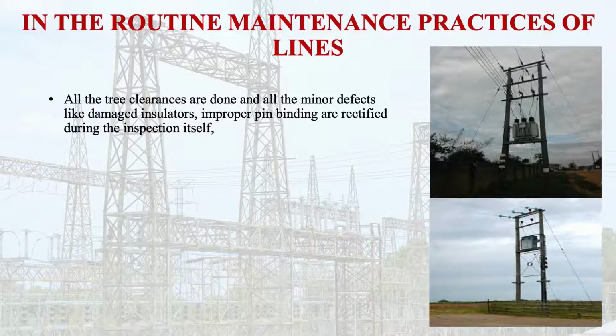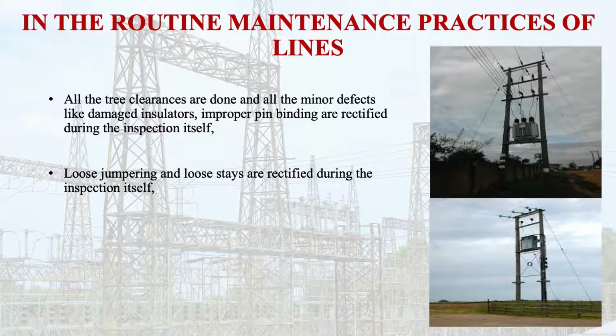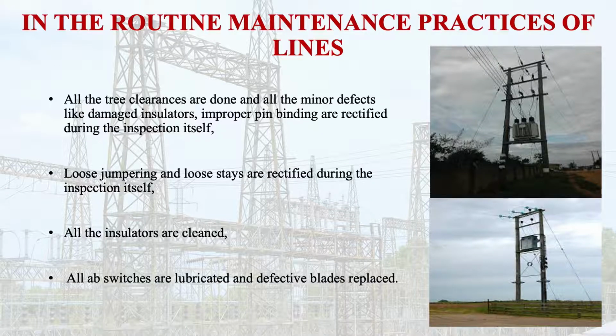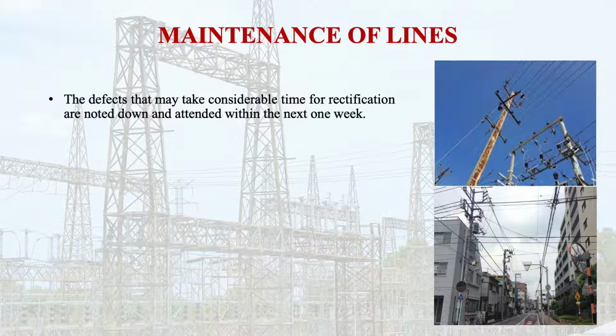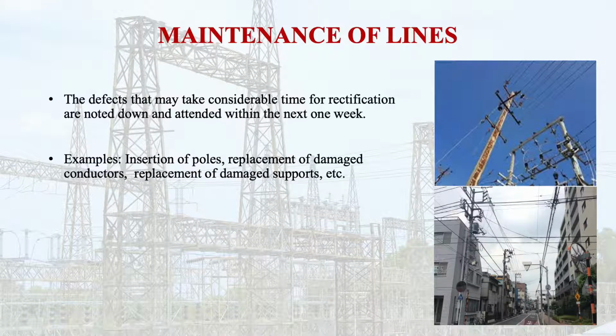In the routine maintenance practices of lines, all the tree clearances are done and all the minor defects like damaged insulator, improper pin binding are rectified during the inspection itself. Then loose jumpering and loose stays are rectified during the inspection itself. All the insulators are cleaned and all AB switches are lubricated and defective blades are replaced. The defects that may take considerable time for rectification are noted down and attended within the next 1 week. For example, insertion of poles, replacement of damaged conductors, replacement of damaged supports, etc.